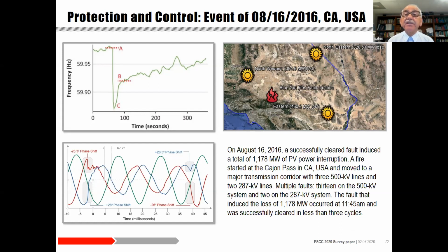And notice that where you see the sign of the sun, there are PV facilities that dropped out because of this fault. In reality, the fault was cleared successfully. As a matter of fact, the fault that caused this blackout was cleared in 3 cycles. Therefore, normally this would not cause any problem, but because of the dip in frequency, which was very minor, about 120 millihertz, and also because the clearing of the fault generated a phase shift in the voltage waveforms, that confused the controls of the PV facilities, if you like to use this naive term, and they dropped the facilities out.